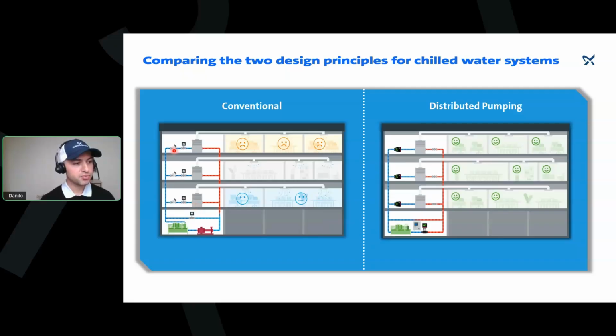And the idea is removing that, utilizing those pumps, and that could be at the inlet or the outlet of your air handler system, right? With that, again, important, you need a decoupler. And here's where we're tracking temperature. We utilize temperature sensors here and start measuring the temperature. So what happens is you reduce all those valves. This pump will run based on differential temperature. It will know the temperature. This is not like one pump needs to communicate with each other. No, they just do that by themselves, by the little sensor I showed you.